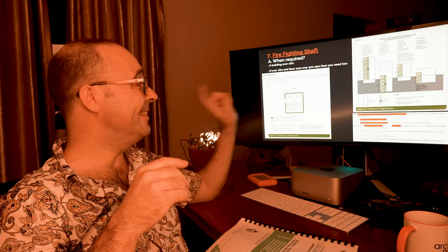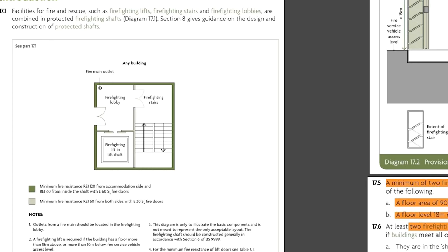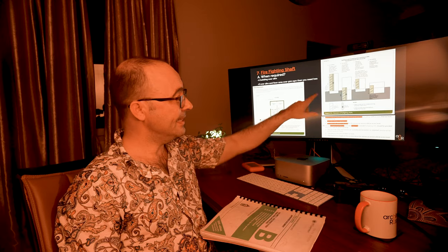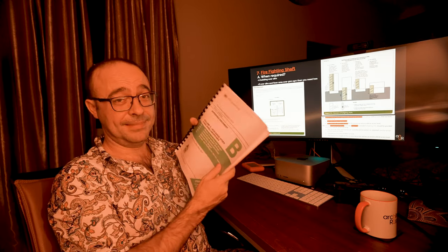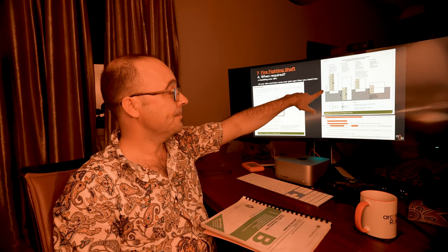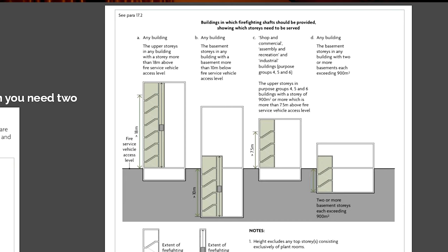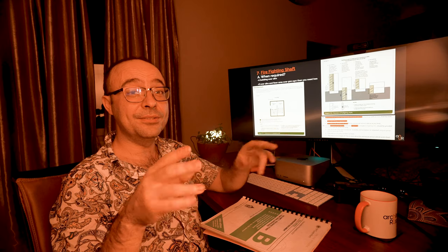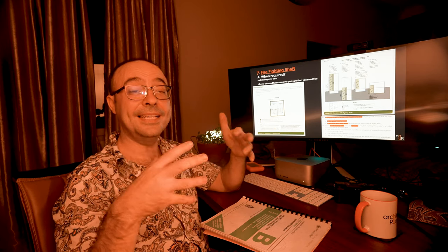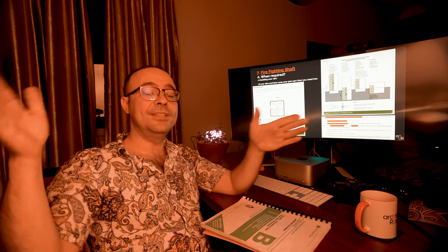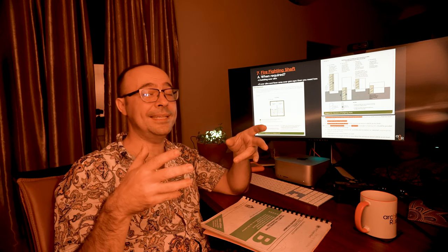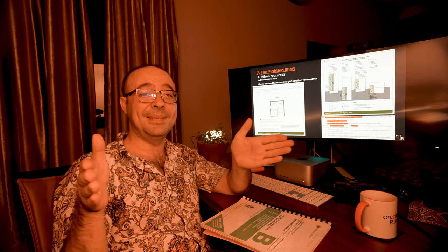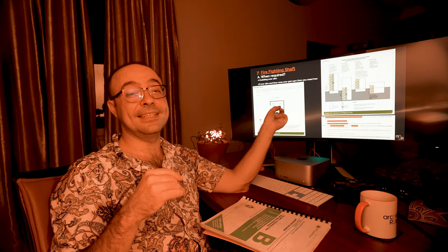Firefighting shaft — any building over 18 meters needs this. It's like a fire escape stair with a lobby and then a fireman's lift as well. Over 18 meters you need one of these. If you've got a basement more than 10 meters, you need one as well. And if the area of the floor is over 900 square meters, you'll need two of them. That's why a lot of the buildings I do are usually under 18 meters and usually under 900 square meters. I did a 20-storey building and kept it under 900 square meters per floor so I wouldn't need two of them.